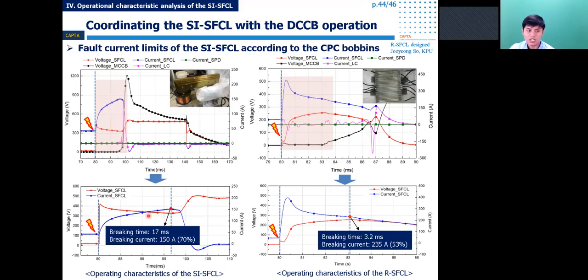In case of using the SFCL, because it has a large inductance, the inductance can reduce the current rising rate, di/dt. So there was no surge current like in the resistive SFCL. Because di/dt is reduced, the circuit breaker can detect and break the fault current more slowly. You can see especially the saturated FCL can greatly reduce the breaking current level, much more than the resistive FCL. Here it can limit the fault up to 70%, and in the case of the resistive, only 53%.